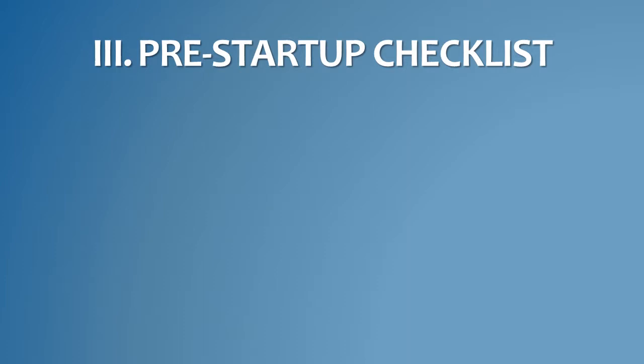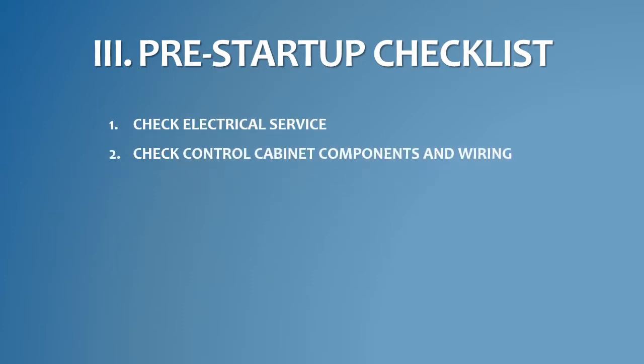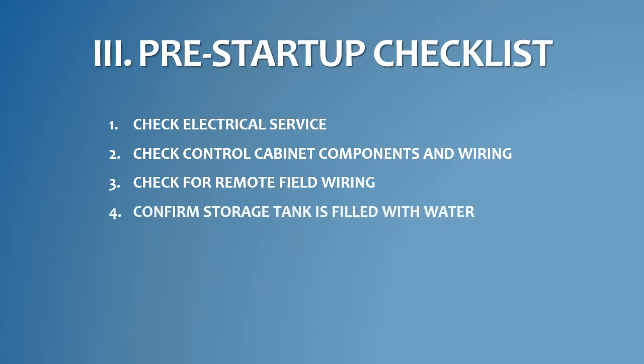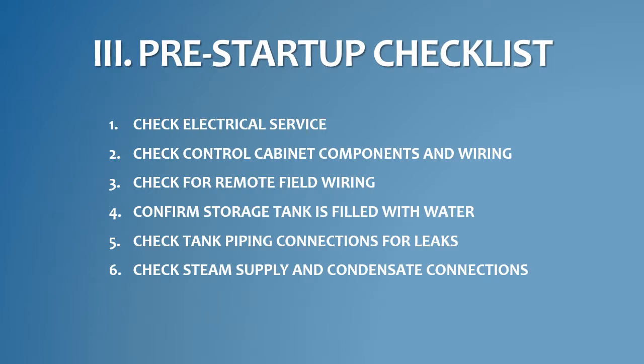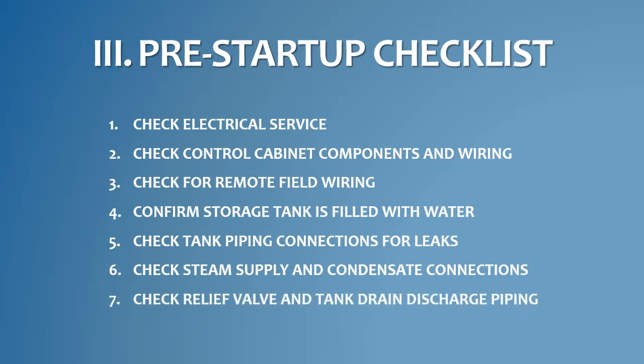safe and reliable manner. Before starting the unit, you will need to check for adequate electrical service, check the control cabinet components and wiring, and confirm if any external control wiring connections exist. You will then confirm the tank is filled with water, check the piping connections for leaks, and ensure the steam supply and condensate return lines are installed properly and that all relief valves and tank drains are plumbed properly. We'll review each checklist item in detail.